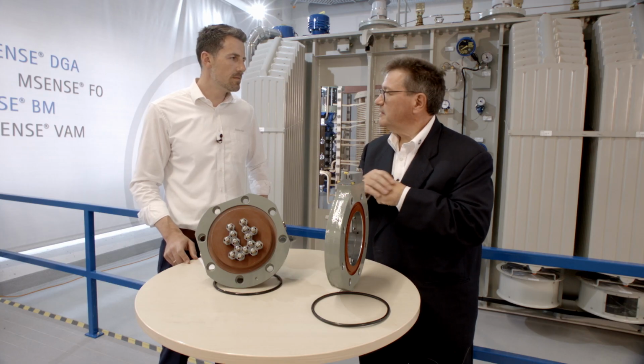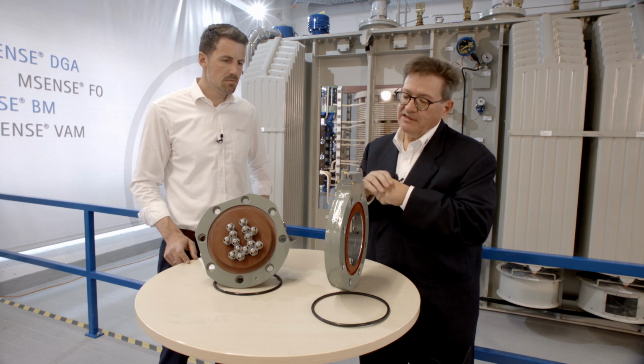And we have many. For example, for the cooling banks, for the radiator banks, there are butterfly valves to be installed to isolate the radiators from the transformer, just in case anybody needs to replace the radiator banks without draining the entire oil in the transformer. So isolation valves of butterfly type are specifically designed for the purpose.